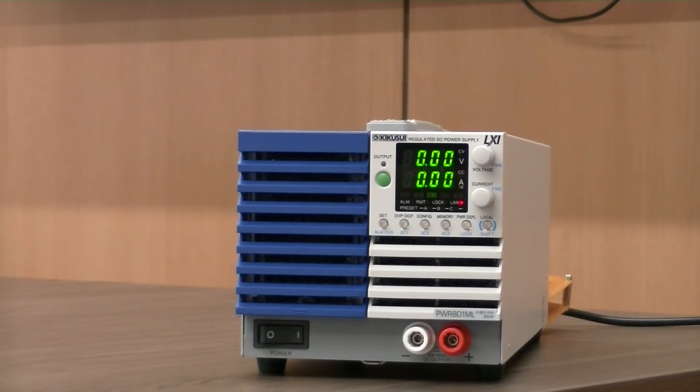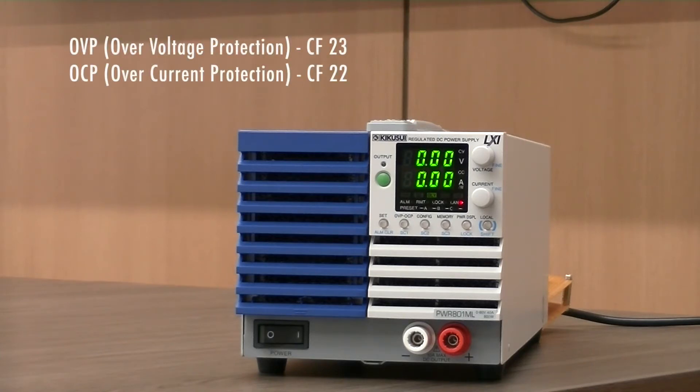As with most programmable power supplies, the PWR01 comes with overvoltage protection as well as overcurrent protection. The current setting limit and voltage setting limit can be easily set from config 22 and 23 respectively.